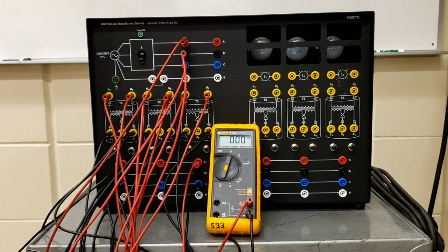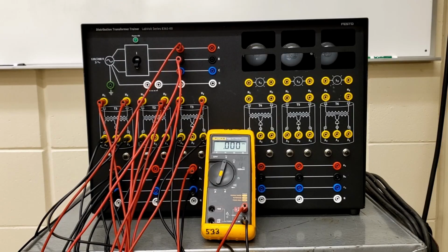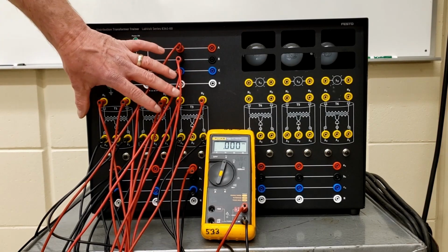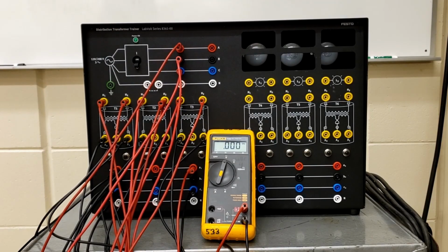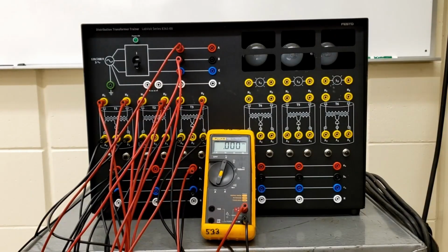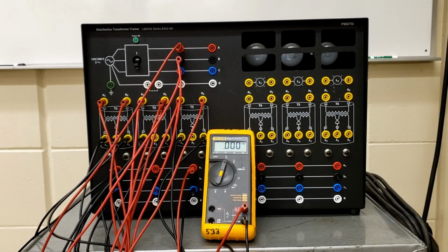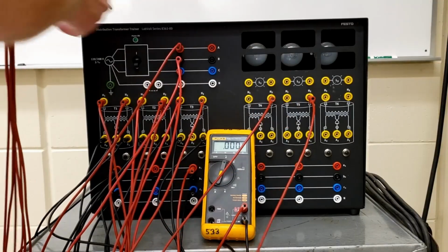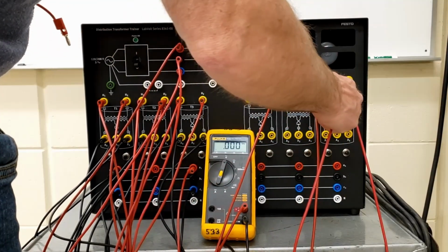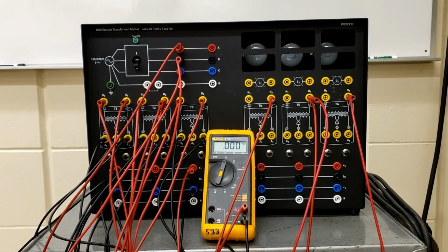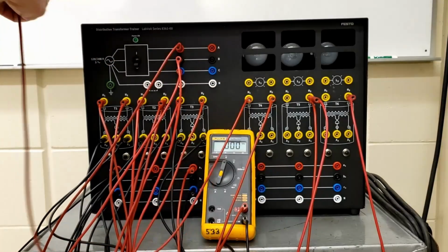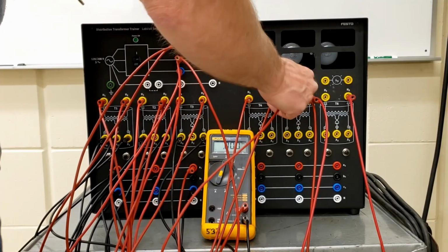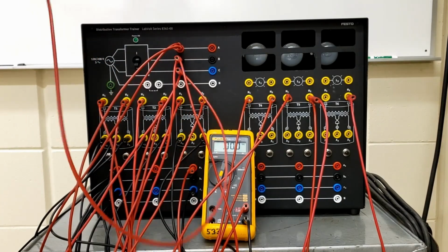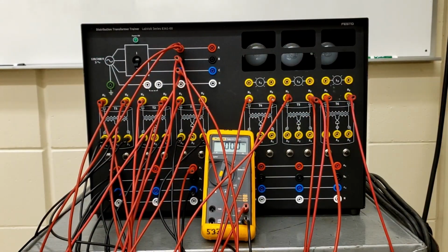Okay guys, next one. We're on page 15 of the student manual and we're on page 18 of the instructor manual. So it says we want to do a Y to delta 30 degrees phase shift versus a Y to delta 210 degrees phase shift. Okay, so let's do the primary for the second bank of transformers there. So it looks like all the H2s are going to tie together again. So primaries are identical in that the H2s are tied together. Okay, now we're going to feed the primaries from A to H1 of the first transformer, so identical to the first guy. B is going to feed our H1 of the second transformer, and C is going to feed the H1 of the third transformer. Okay, so primaries are done there for the Y.